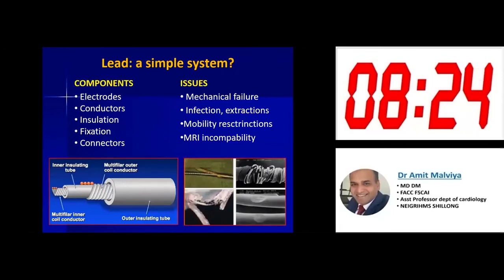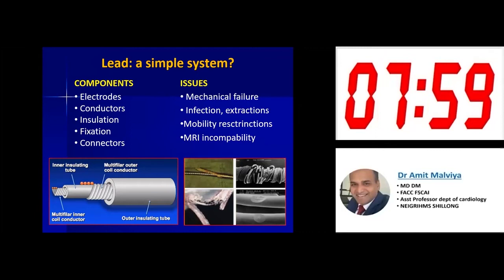So the basic thing in a pacemaker system is a lead. The lead has many components like conductors, electrodes, insulation, fixation, and connectors. But there are many issues with these conventional leads. Sometimes we end up with mechanical failure, like breakage of the lead or failure of the insulation provided with the lead, leading to pacemaker malfunction.